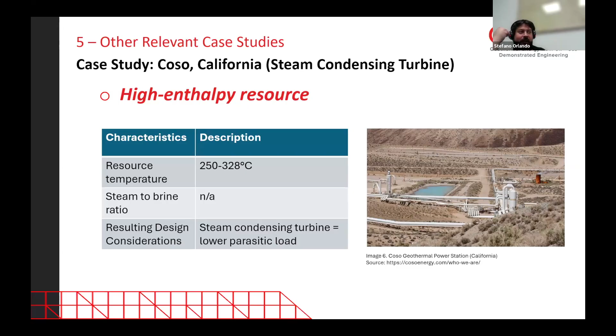And in Coso, they also tried full injection of the non-condensable gases. And then I think there were some issues, because the non-condensable gases were coming back into production, increasing the content, and the gas removal system was undersized. So they decided not to do that again.